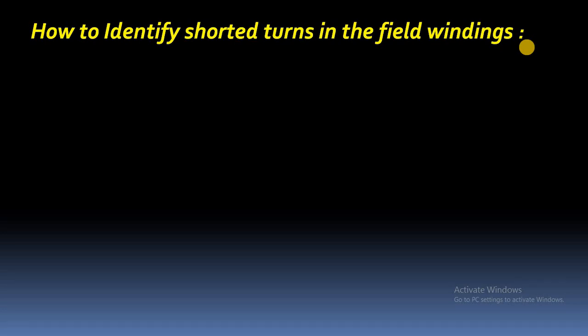In this video we will see how to identify the shorted turns in the field winding using the online technique — the real-time monitoring technique. In the previous video we discussed about the pole drop test, which is an offline method to identify the shorted turns in the field winding. Before going to the online technique, let us briefly discuss how these field shorted turns exist.